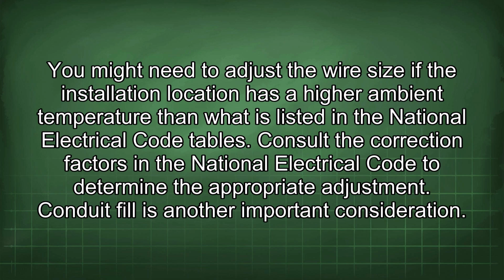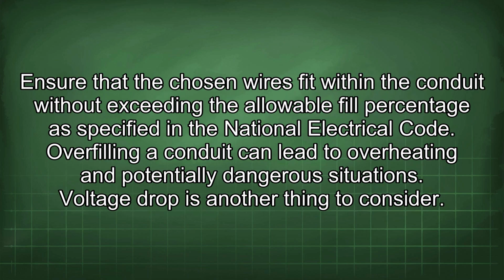Conduit fill is another important consideration. Ensure that the chosen wires fit within the conduit without exceeding the allowable fill percentage as specified in the National Electrical Code. Overfilling a conduit can lead to overheating and potentially dangerous situations.